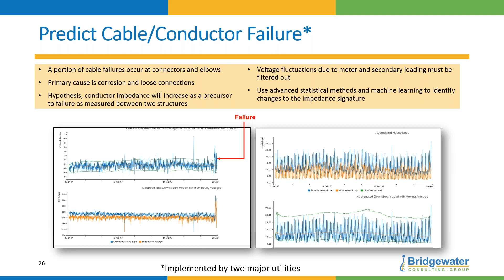The next one is about the smart grid, distribution automation, the modern grid. What we're trying to do is use modern techniques to improve reliability, improve safety, reduce losses, and do all kinds of good things. A lot of those activities involve doing a load flow model in real time. Load flow models have limitations—a lot of them are based on estimated impedances of wires and a known circuit connection that may have changed over time down at the residential level.